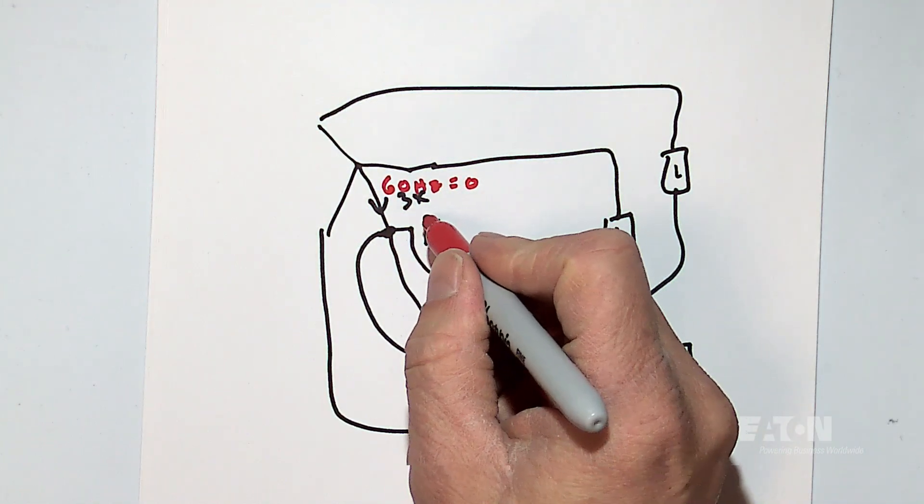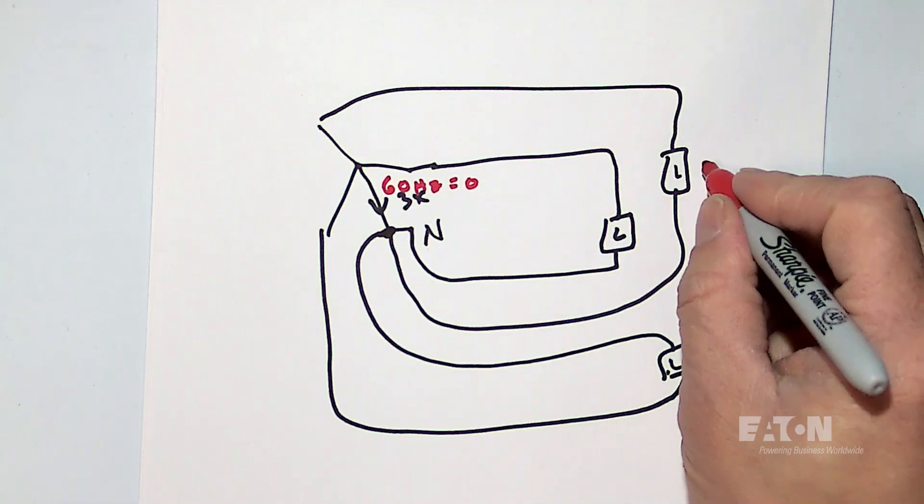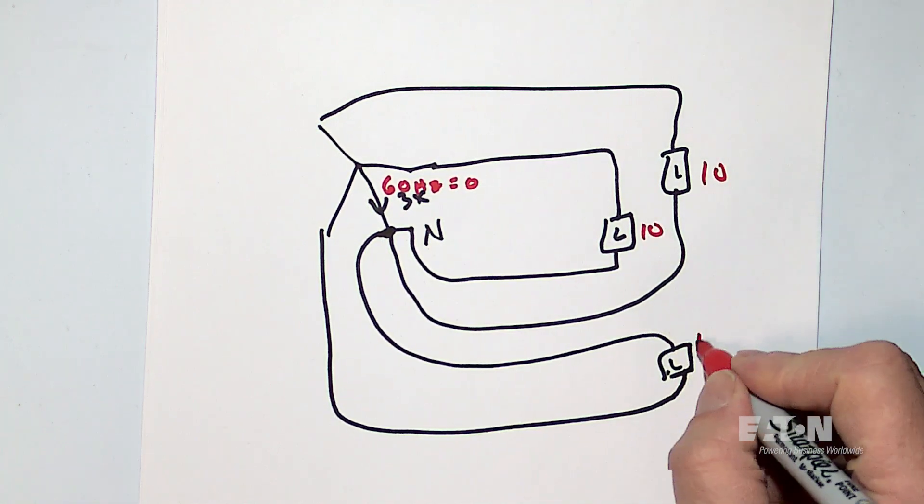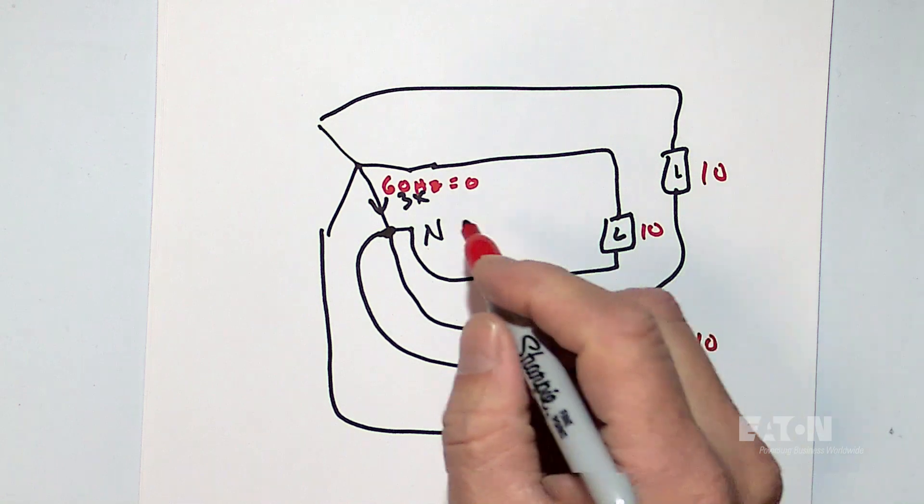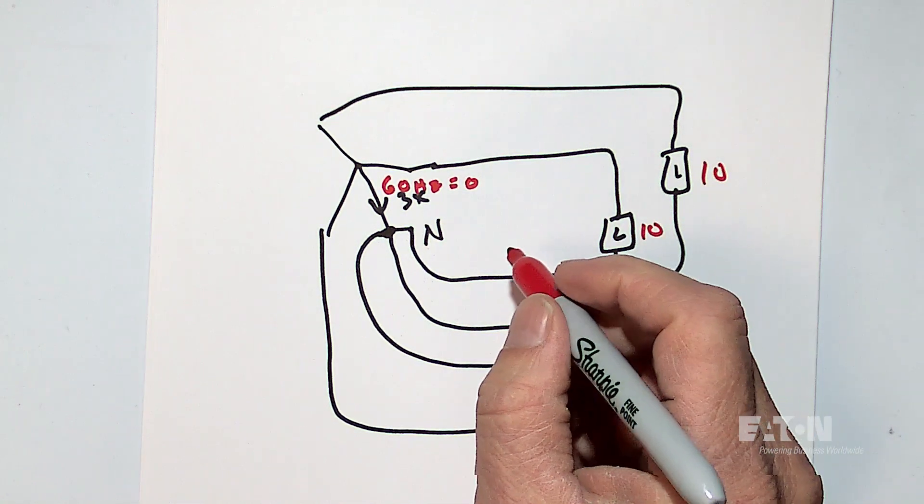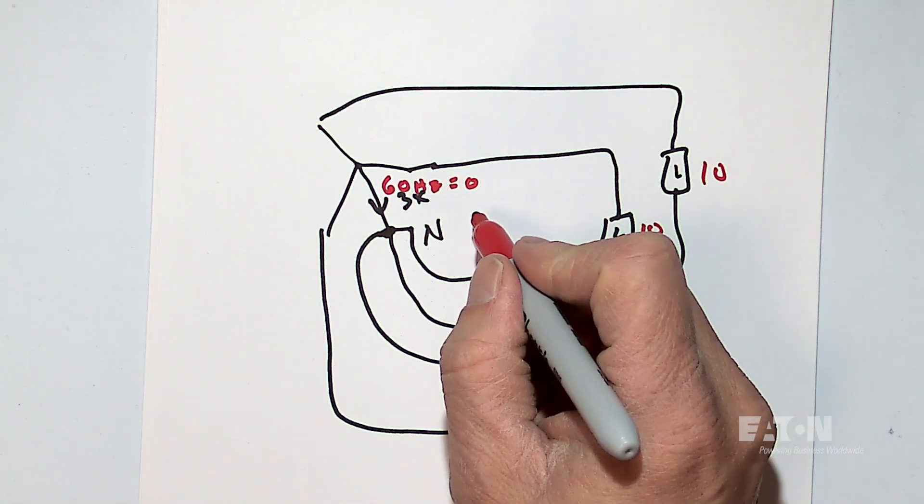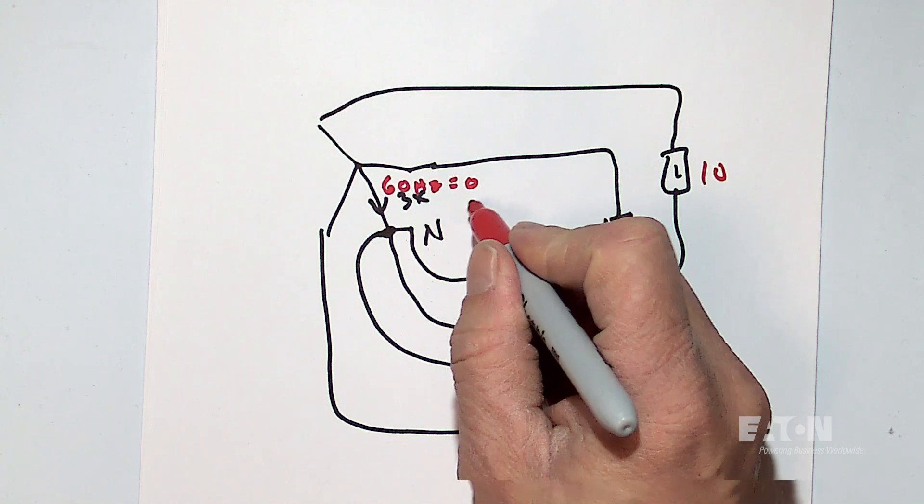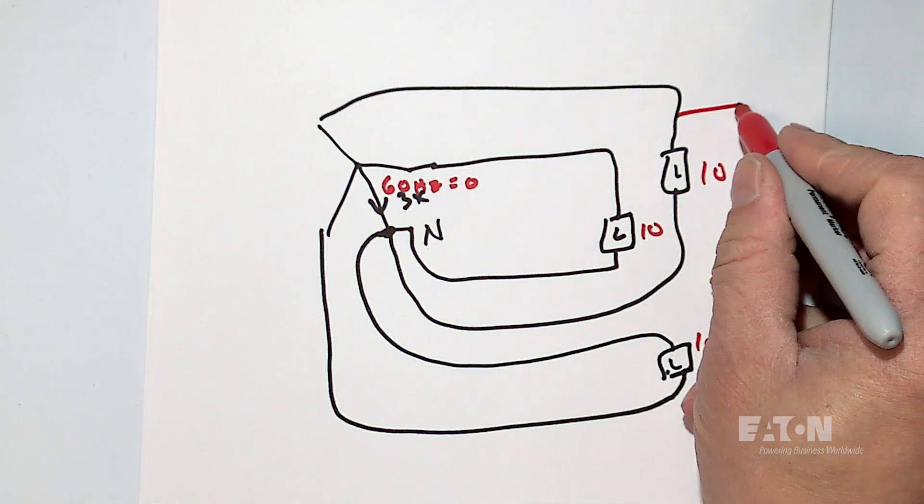But third harmonic could be three times that. So again, if we go 10 amps on each phase, and let's just say the 60 hertz mostly added up to zero. But let's say there was a little bit left on phase A just from another single phase load that was over here, maybe.